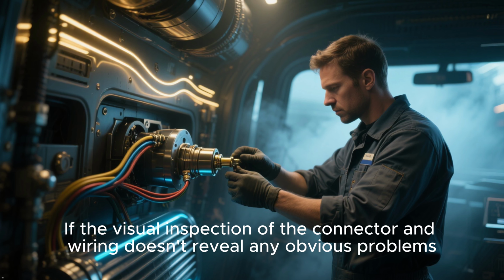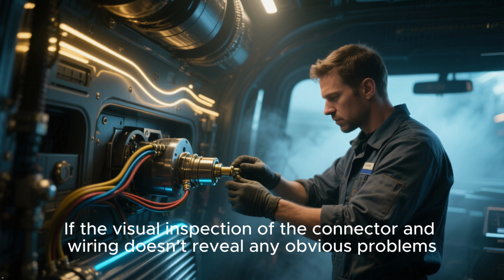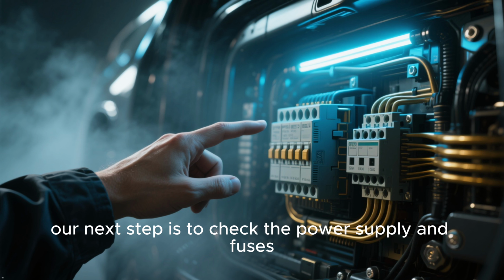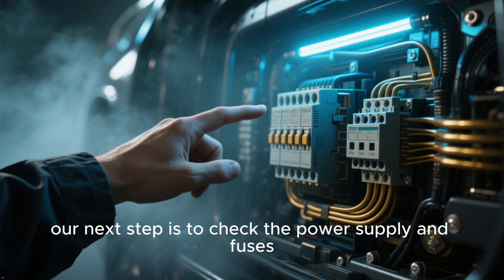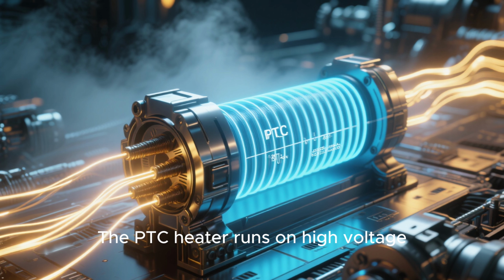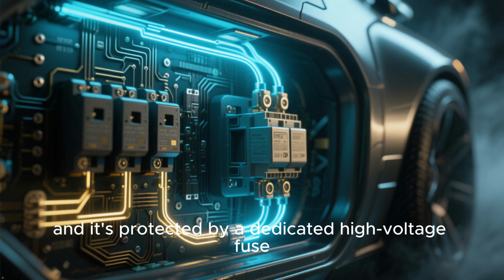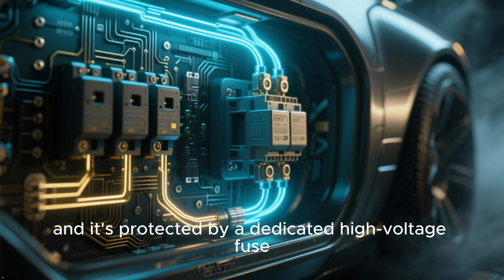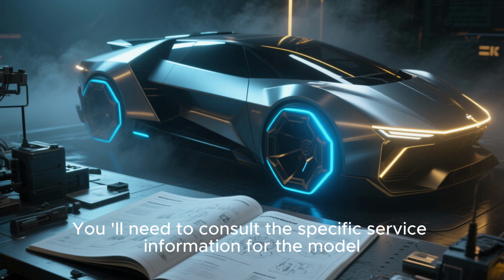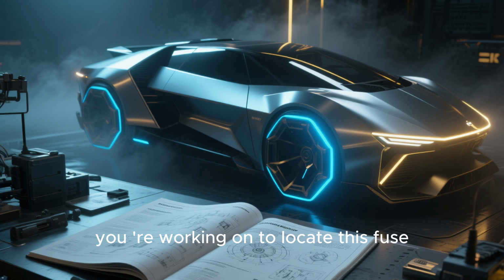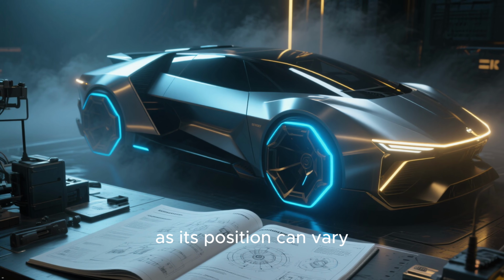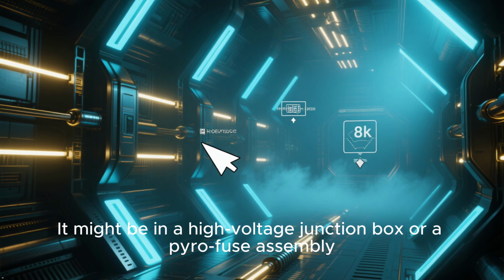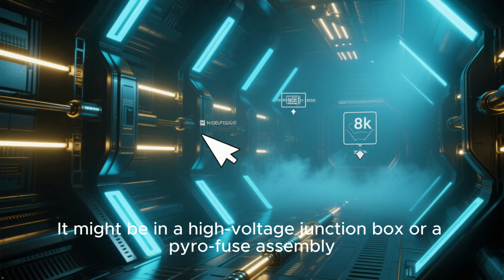If the visual inspection of the connector and wiring doesn't reveal any obvious problems, our next step is to check the power supply and fuses. The PTC heater runs on high voltage, and it's protected by a dedicated high voltage fuse. You'll need to consult the specific service information for the model you're working on to locate this fuse, as its position can vary. It might be in a high voltage junction box or a pyrofuse assembly.